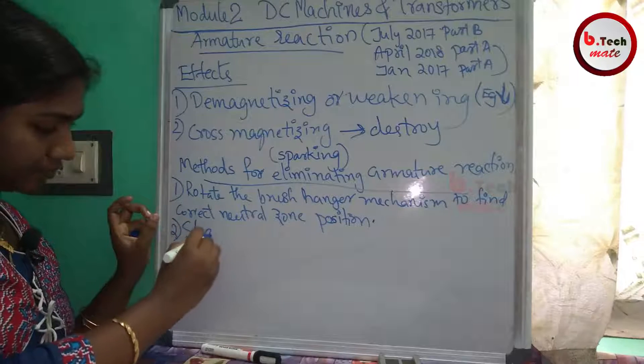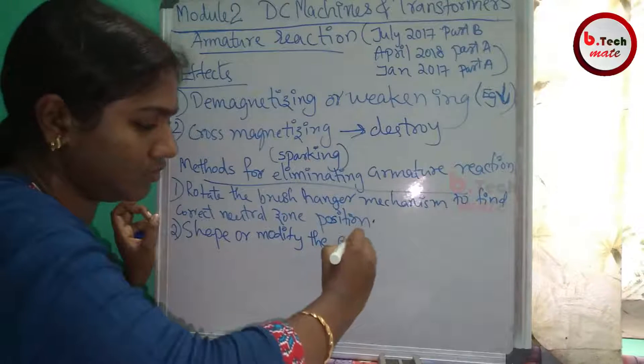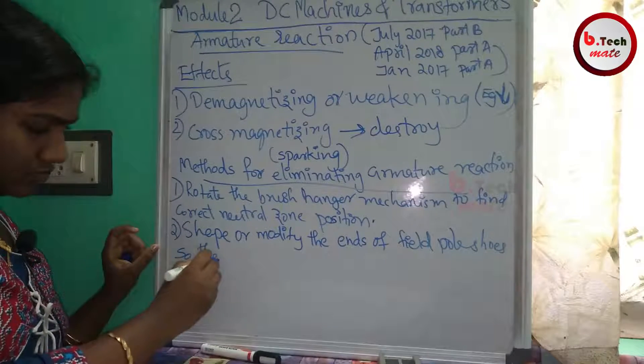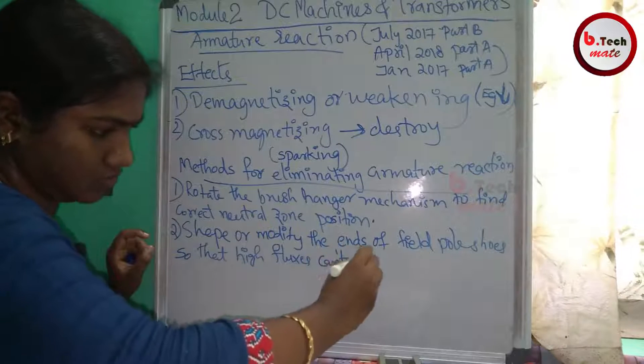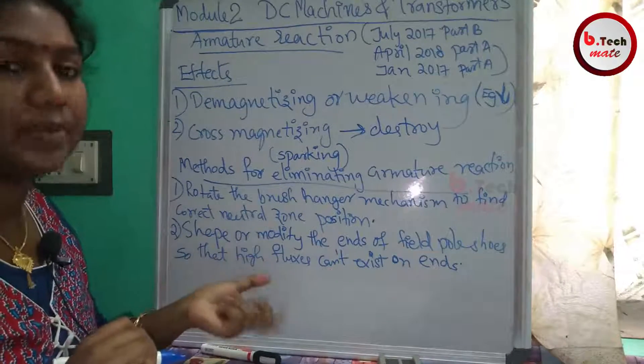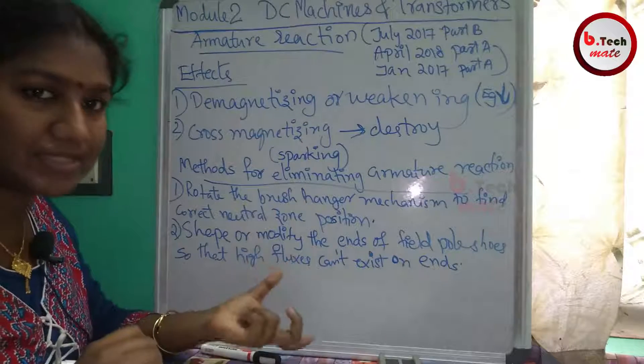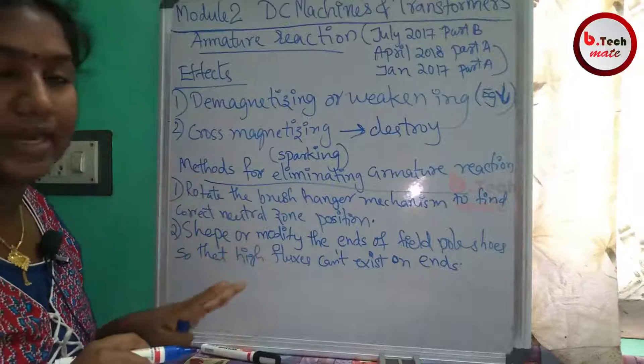The second method is to shape or modify the ends of the field pole shoes so that high flux concentrations cannot exist at the ends. By modifying the field pole shoes and adjusting their shape, we can reduce armature reaction.